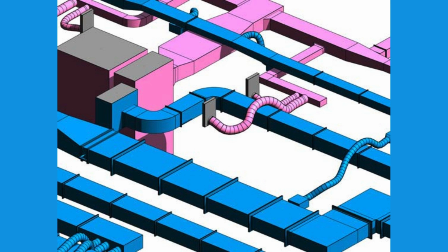2. Duct sizing and layout. Once the airflow requirements are established, ducts are sized to deliver the required amount of air with minimal pressure loss. Round ducts are generally preferred for their lower pressure drop compared to rectangular ducts, however rectangular ducts can be more practical for fitting into tight spaces.